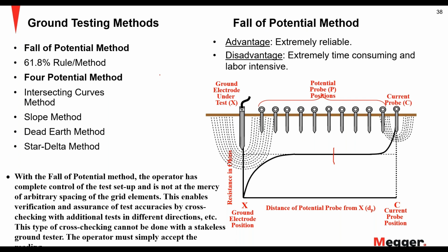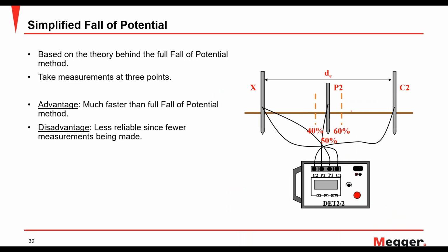Advantages of the fall of potential method, and the 62% one, is it's extremely reliable. Disadvantage, it is extremely time consuming and labor intensive. When you are measuring 3-pole, you have to measure for 62%, go there, dig up the ground rod in there and measure it that way, and you have to do it at several different points. So what's the alternative? You can use simplified fall of potential. Basically, you make 3 different measurements at 40, 50, and 60%, and then you take an average of those measurements, and you can use that as your grounding rod measurement. The advantage is being much faster and simpler than a full fall of potential method, but it is less reliable since fewer measurements are being made. So it's less accurate, but it serves the purpose rather than doing a full fall of potential method.